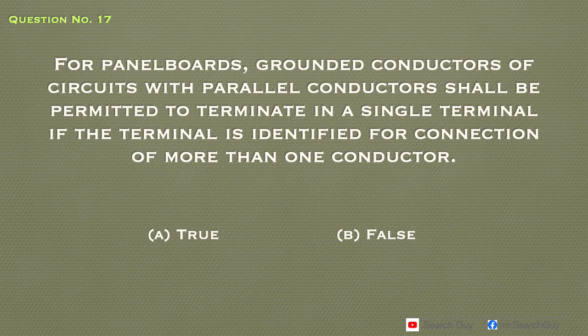Question number 17. For panel boards, grounded conductors of circuits with parallel conductors shall be permitted to terminate in a single terminal if the terminal is identified for connection of more than one conductor. A. True. B. False. Answer. A. True.